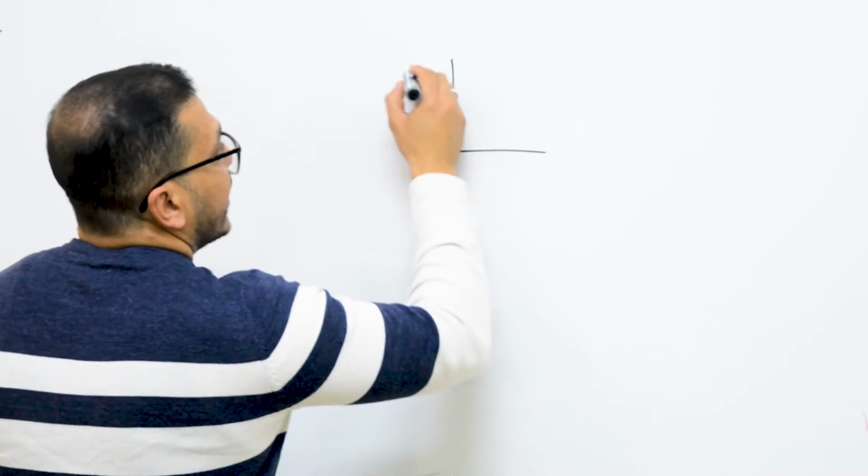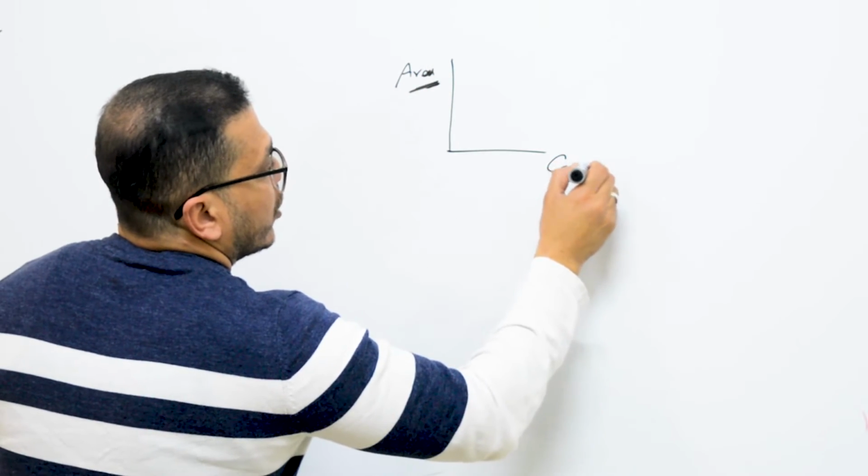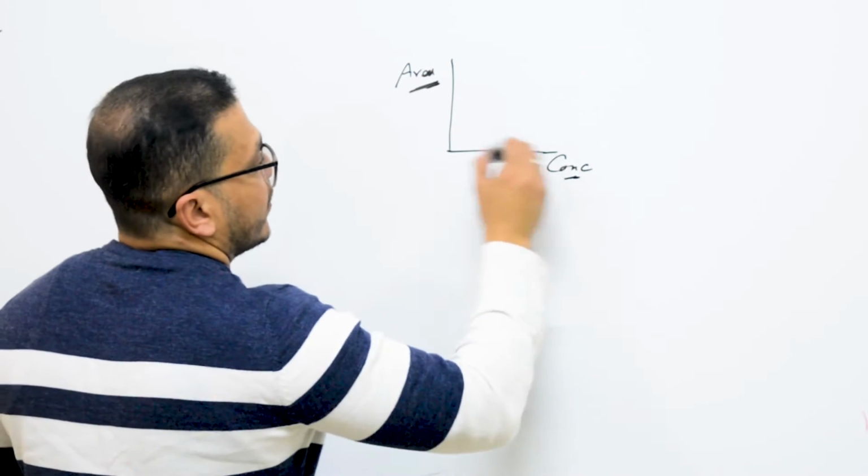As you know, calibration is used to quantify the concentration of target analytes in the unknown matrix or unknown sample. So you will prepare different calibration standards, and the instrument will create a calibration curve containing these concentrations, and you will have the relation between the area and concentration of your calibration standards.